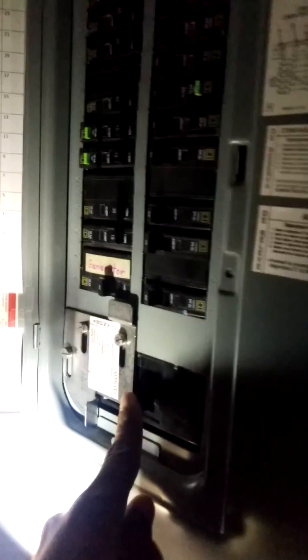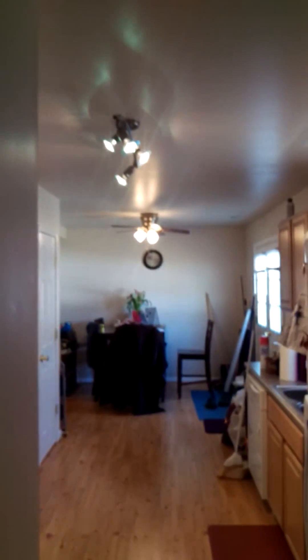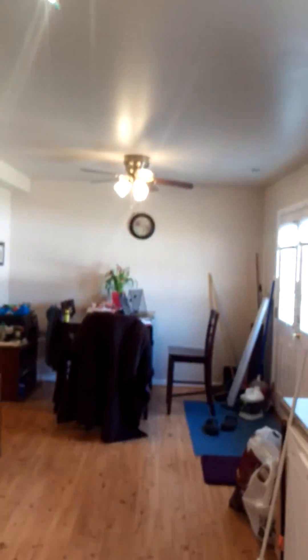The fridge is even on — well, the fridge is dead. Come in here. The generator's running and the main is off. The interlock is down. Now turn on the generator breaker — that's all wired up from a while back. Just turn it on and look — we got lights! We even got the internet. Lights on. And we're on generator power.